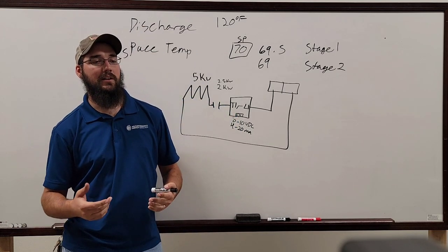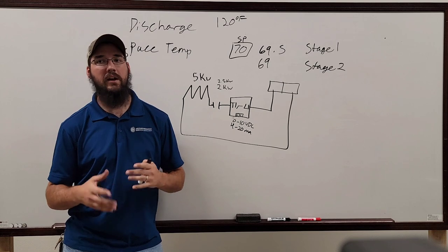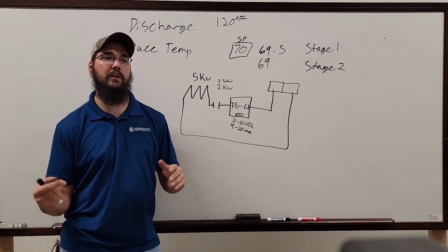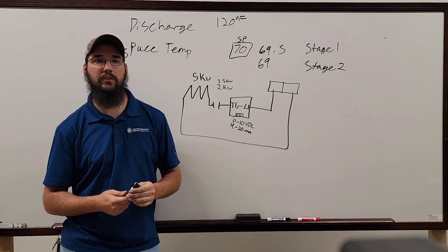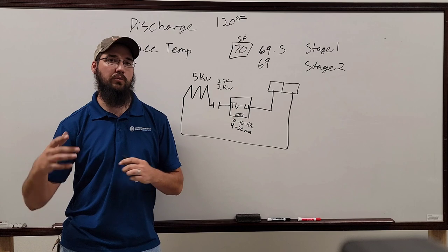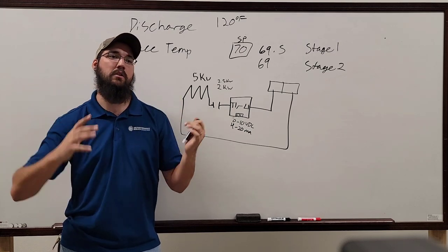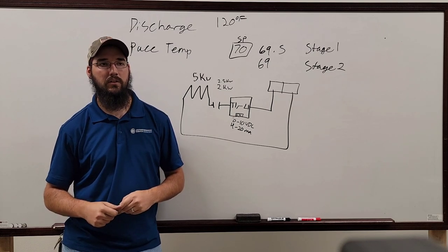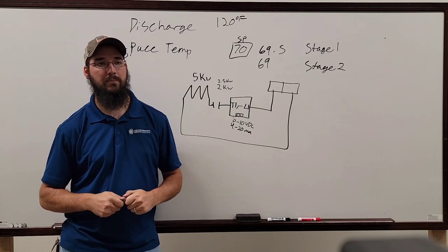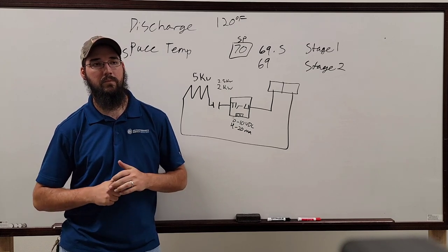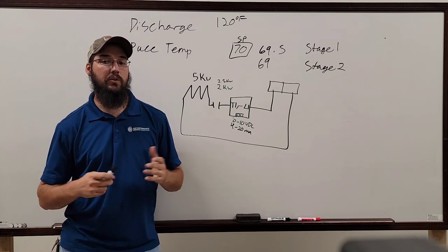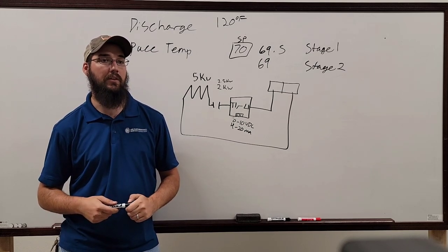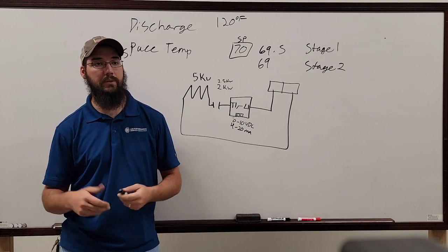So, single phase SCRs, I've not had as much trouble with. And it's not as simple as just going and installing a second SCR to hit the other phase, all right? Don't think you're going to outsmart how the system is going to function, because it's not that easy. Well, he did put two single phase SCRs on the two legs to control the same voltage. So you'd have to set it up and install it appropriately. And then, yeah, the gates would need to be in sync.